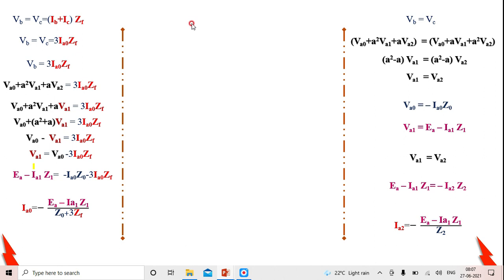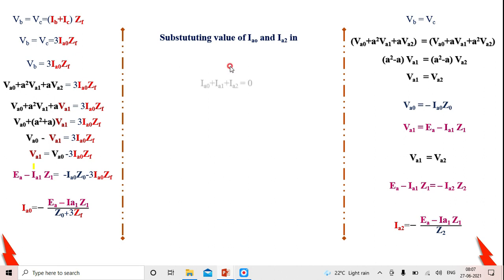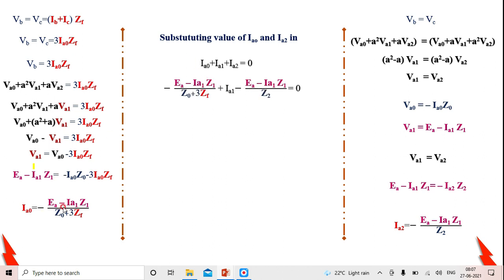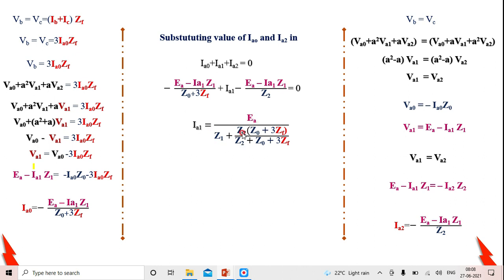Applying the boundary condition Ia = 0, i.e., Ia0 + Ia1 + Ia2 = 0, and substituting Ia0 and Ia2 in terms of Ia1, we have only one variable Ia1. Solving this equation, the positive sequence current is: Ia1 = Ea / [Z1 + (Z2·(Z0 + 3·Zf)) / (Z2 + Z0 + 3·Zf)].